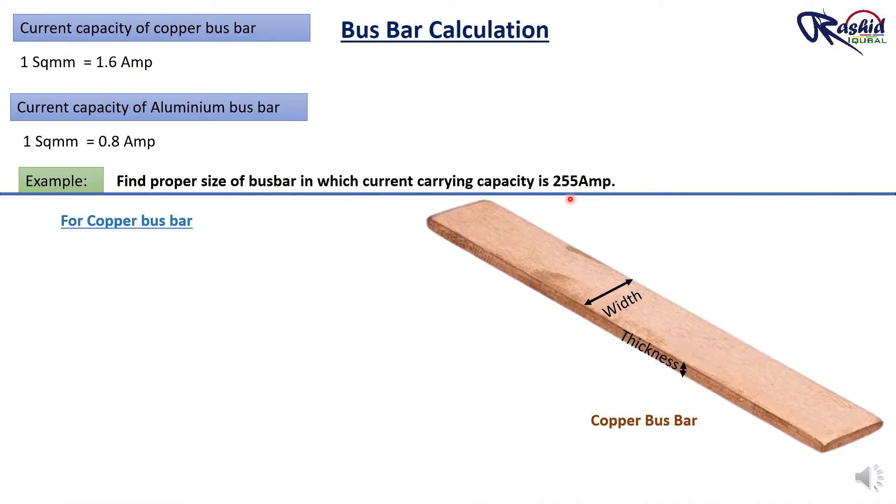And 1 square mm copper current carrying capacity is 1.6 ampere as I said. Through these inputs, we can calculate total area of copper which can carry 255 ampere current. So area of copper conductor equal to 255 divided by 1.6 equal to 159.3 square mm. That means we required 159.3 square mm copper to carry 255 ampere current.